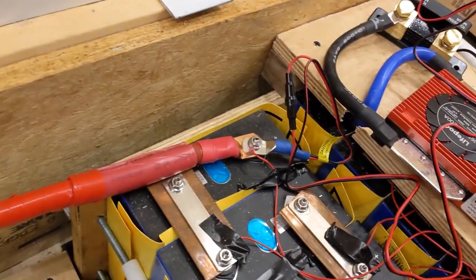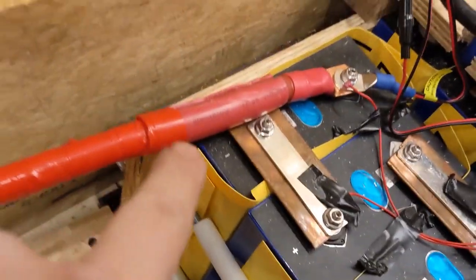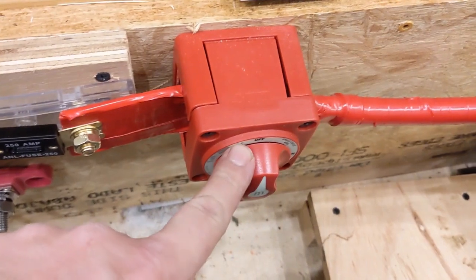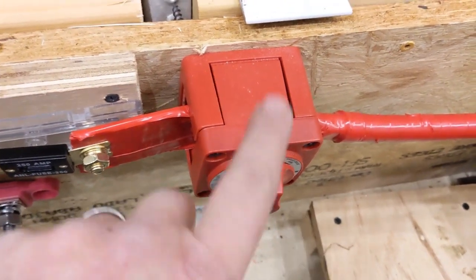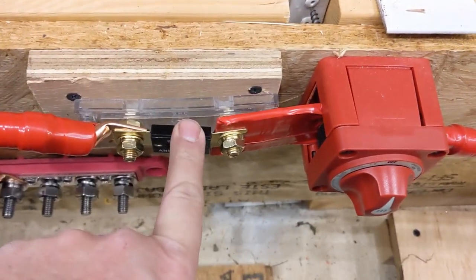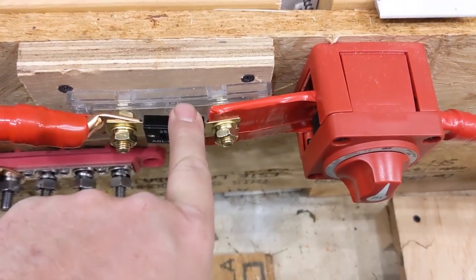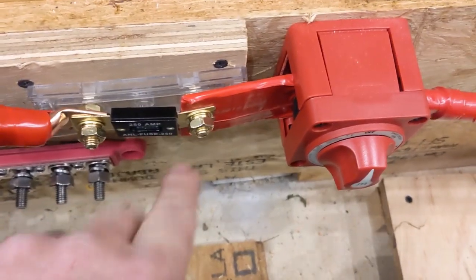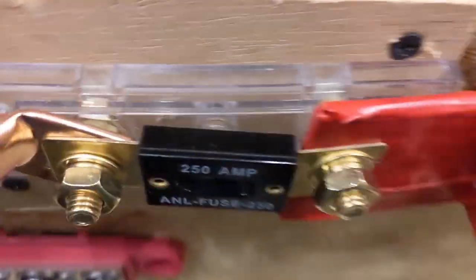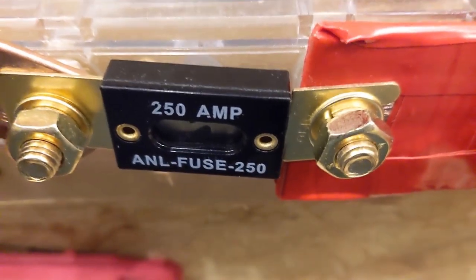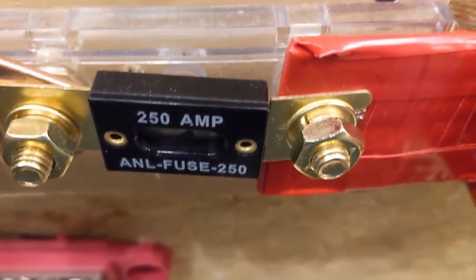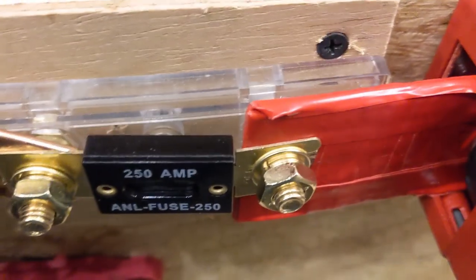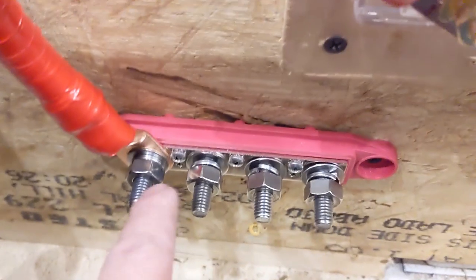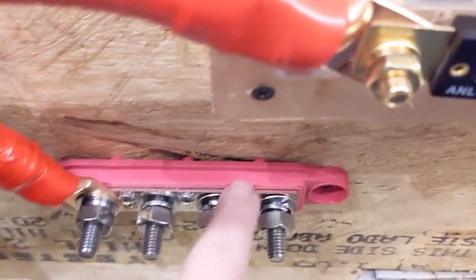Alright, so I've got the positive side protected like I showed you, going to a marine battery shutoff switch. I did this ahead of the fuse because you need to change the fuse, and you don't want current going to it when you're changing it. So I put the ANL fuse in place. This is a 250 amp fuse. I don't expect more than 100 amps of draw out of this battery pack most of the time. We've got this going to the positive bus bar down here, locked down, screwed in place.